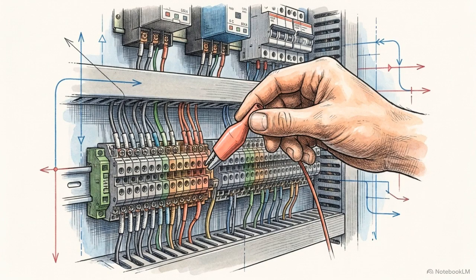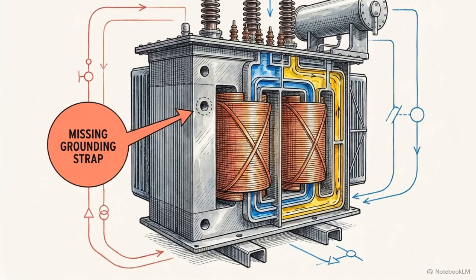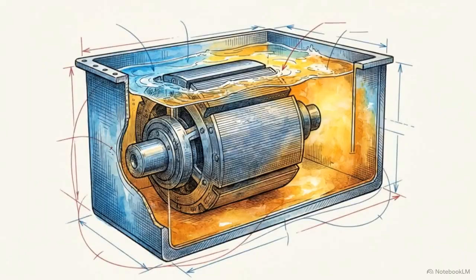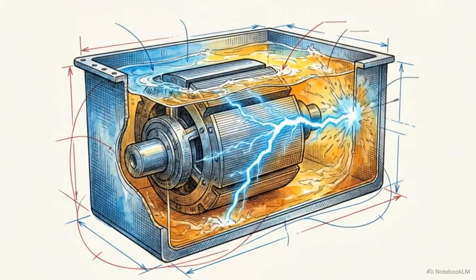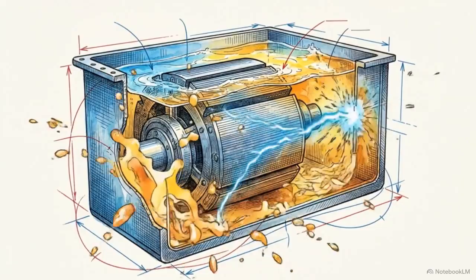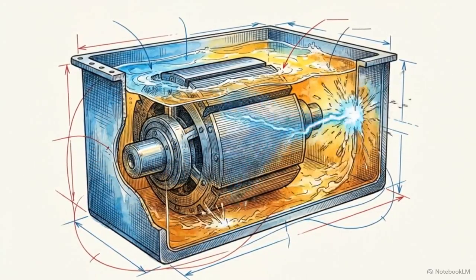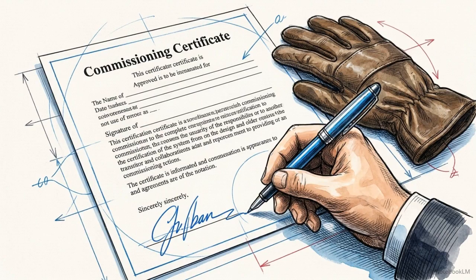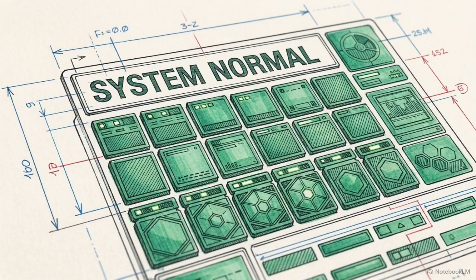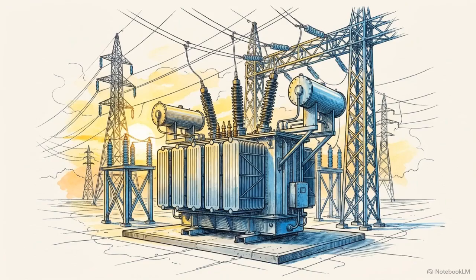If a technician forgets to reinstall the core earth link, the massive steel core remains ungrounded. Upon energization, it will charge like a capacitor until a violent electrical arc tears through the insulating oil to reach the grounded outer tank. Only when the site witness confirms full physical restoration, complete isolation, and 0 standing alarms on the control board is the asset finally released for its first live voltage grid synchronization.